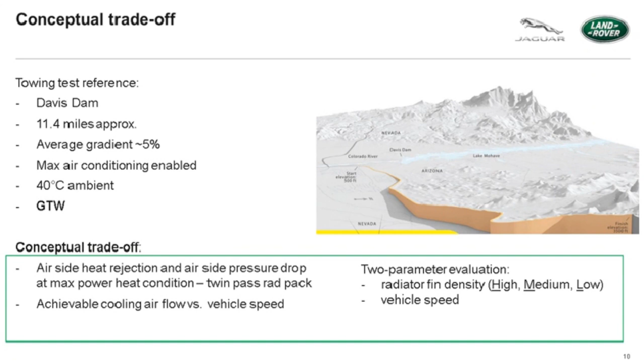But based on this type of test, we can look at the trade-off in heat rejection and the airside pressure drop for a twin pass radiator pack. For the work presented here, this is done at 3 standard fin densities. We simply refer to it here as high, medium, and low. And the high fin density has the higher UA value. So the simple question we're trying to answer here is, how is heat rejection affected by different configurations, and what happens when we consider cooling airflow versus vehicle speed?